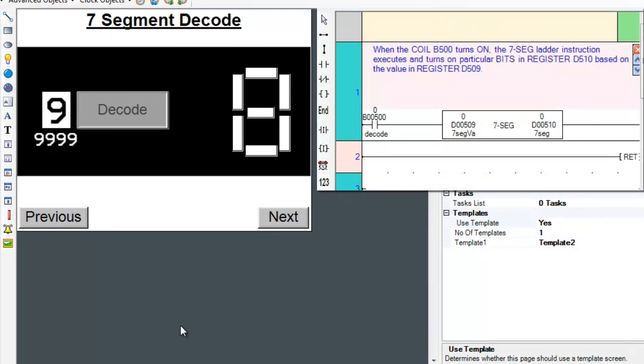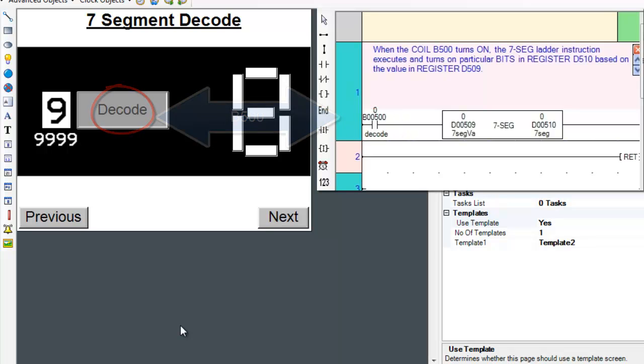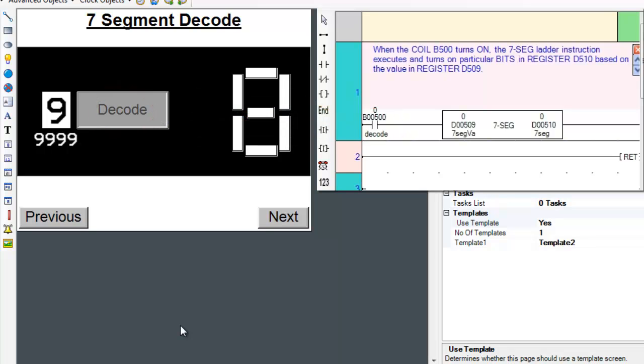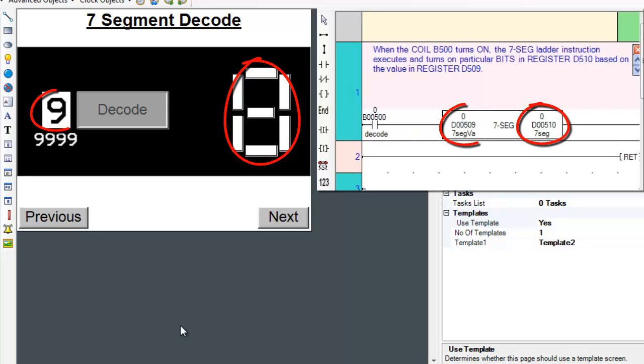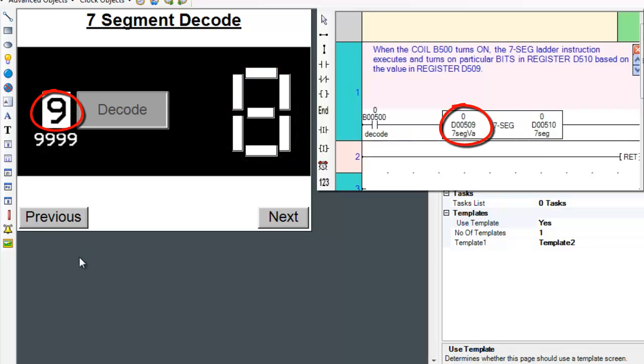How the 7-segment decode instruction works is fairly simple. The instruction will execute when the B500 coil is turned on. The instruction will turn on or off a sequence of bits in a 16-bit register based on the value in register D509 or operand A.